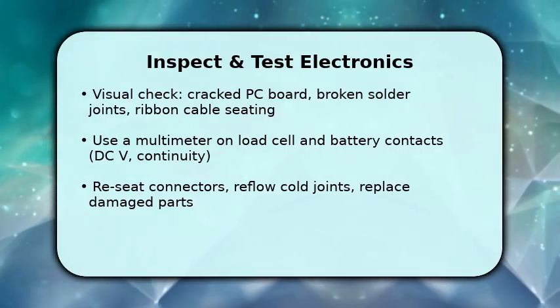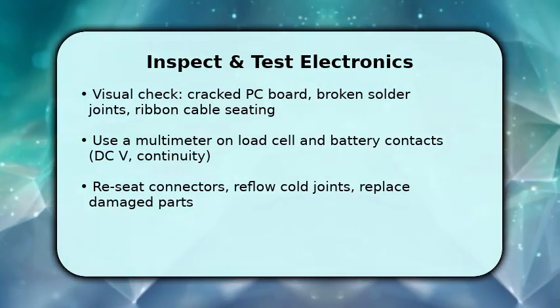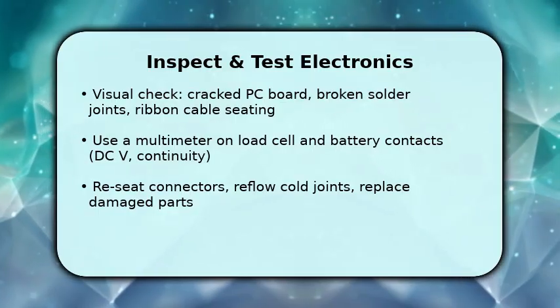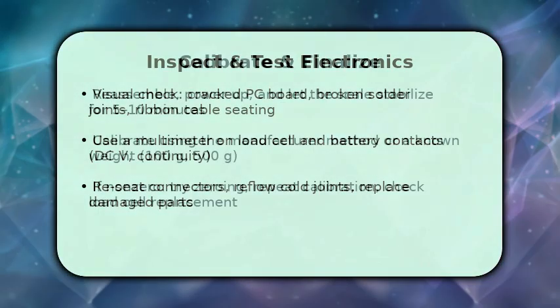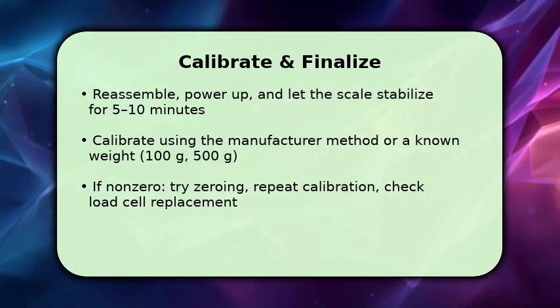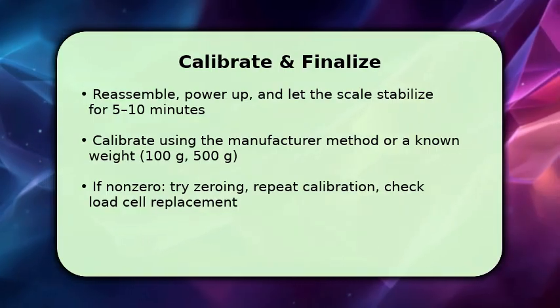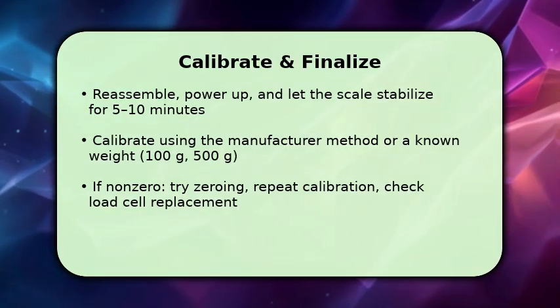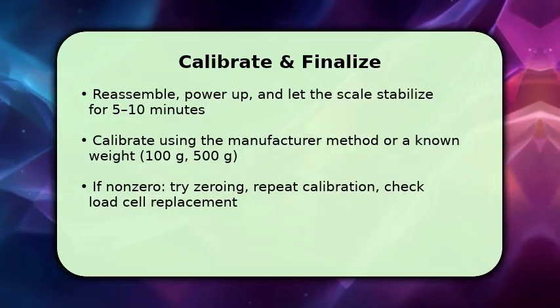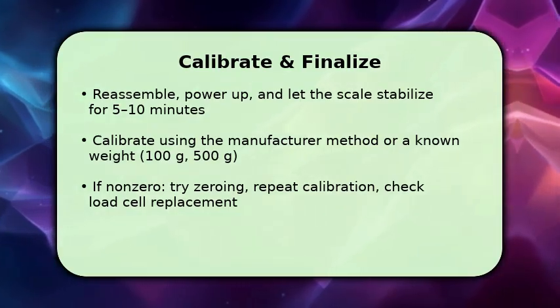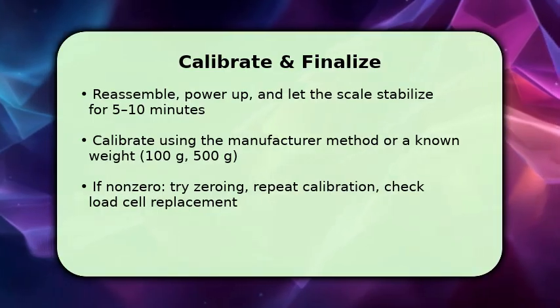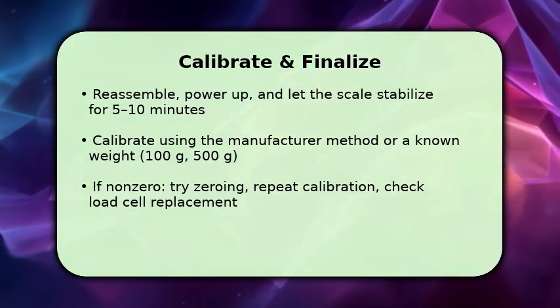Now reassemble and power the unit, allowing electronics to stabilize for 5 to 10 minutes so temperature and drift settle. You'll run the calibration routine, follow the manufacturer buttons, or use a known weight like 100G or 500G. Calibration aligns the ADC to the load cell output. Make sure to zero the scale before placing calibration mass.